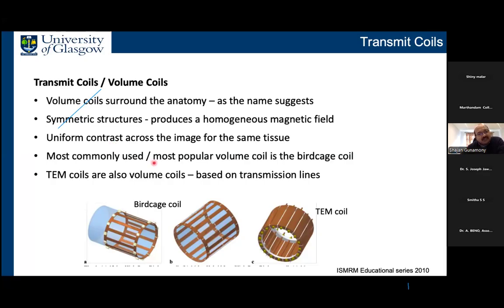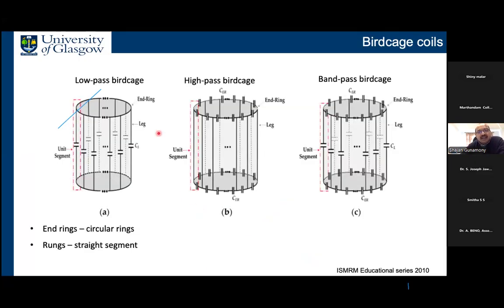And there are two types of volume coils. These are called TEM coils and birdcage coils. The TEM coils are made of transmission lines, and they are typically used at high frequencies. And the most commonly used volume coil is called a birdcage coil because the structure really looks like a birdcage. And there are three different types of birdcage coils. They are called low pass, high pass, and band pass.